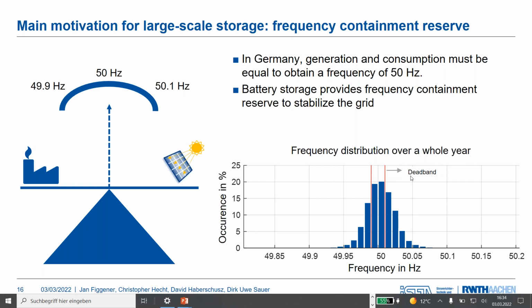This so-called dead band offers the possibility for battery storage operators to provide FCR if they want, but they don't have to. So most of the time they could also not provide it, but you can use, for example, the deadband to recharge the battery and for SOC management, because from time to time the SOC range comes into critical parts and then you have to recharge the battery again or to discharge it. So when there's under frequency, you have to discharge the battery, and when there's over frequency, you have to charge the battery.